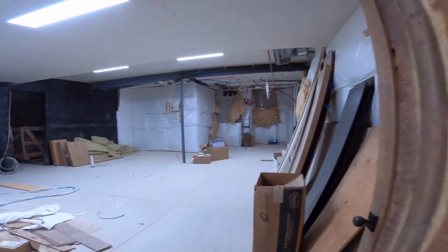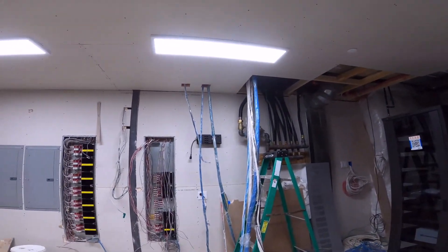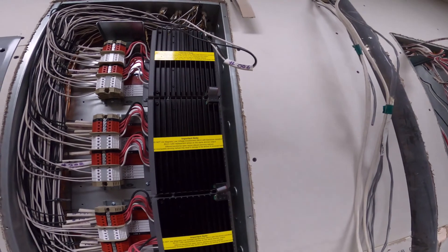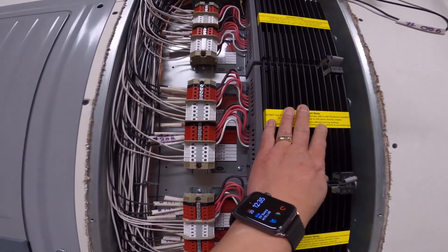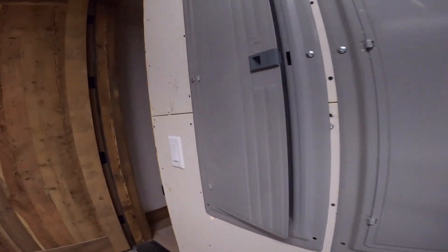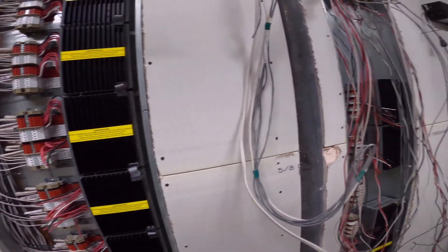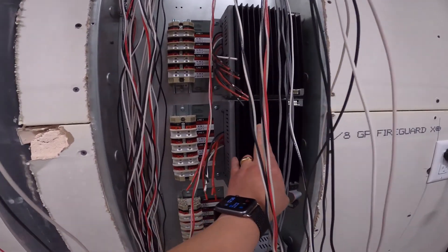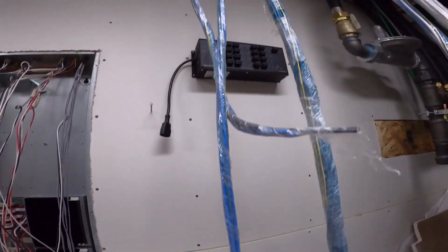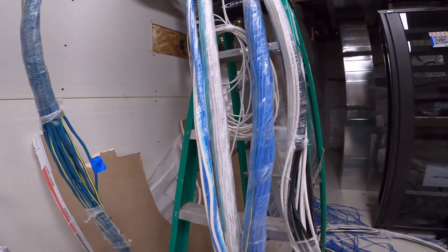This is one of the nicest mechanical rooms I've been in — it's pretty big too, you could practically live in here. So here's where we are right now: we have lighting panels at this house, nice and tidy, wired down to modules. These are dimming modules — they do eight loads, four and four. When you hit a keypad on the wall, it basically talks through the Crestron system and turns on the right loads. We have some relay modules here for high-inrush loads, fans, things like that. That's our Crestnet power module.